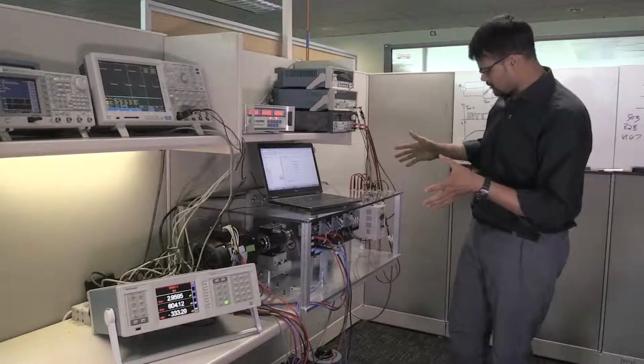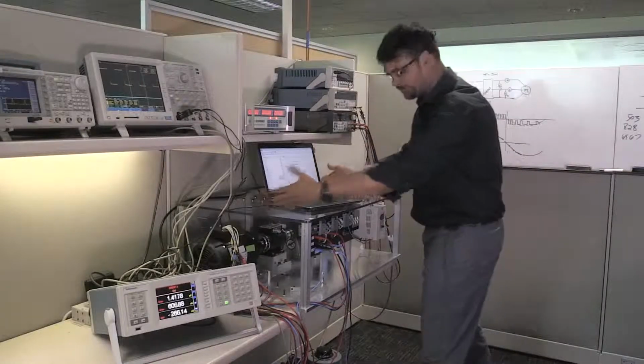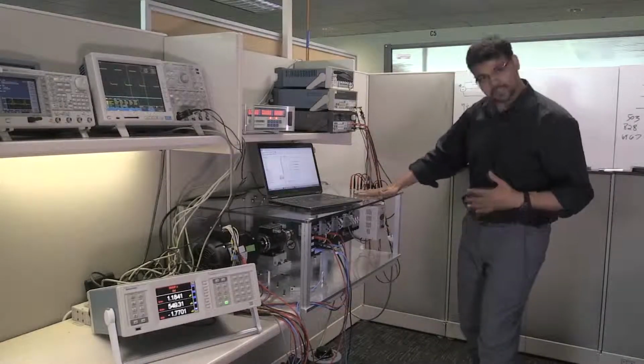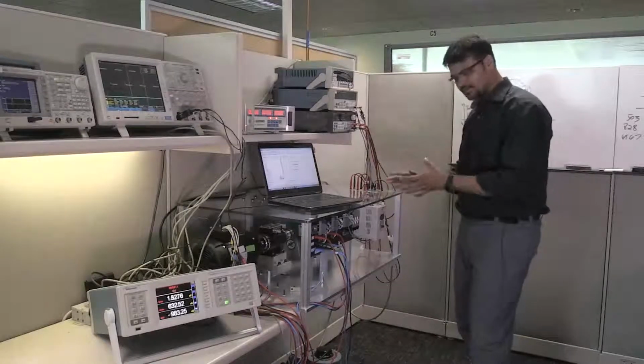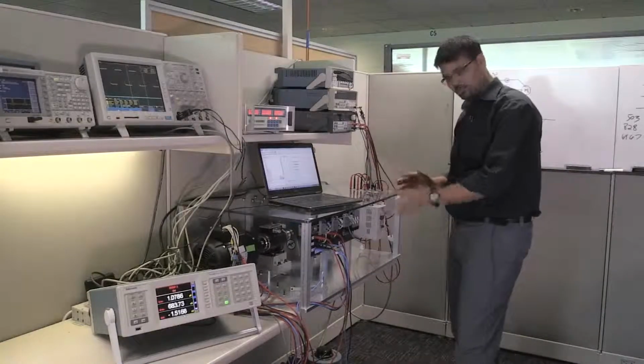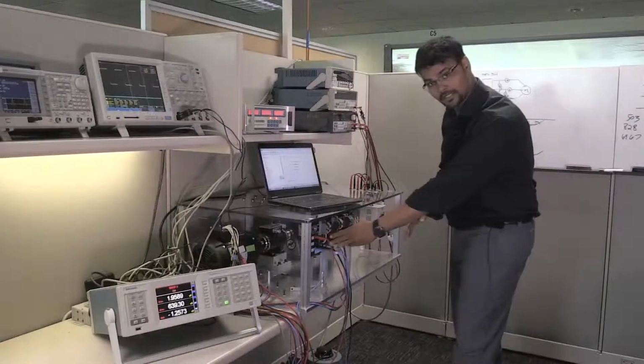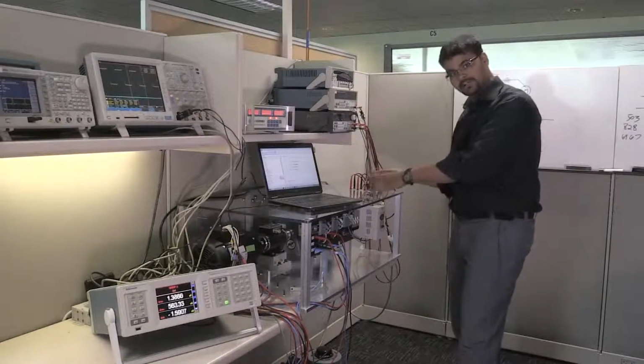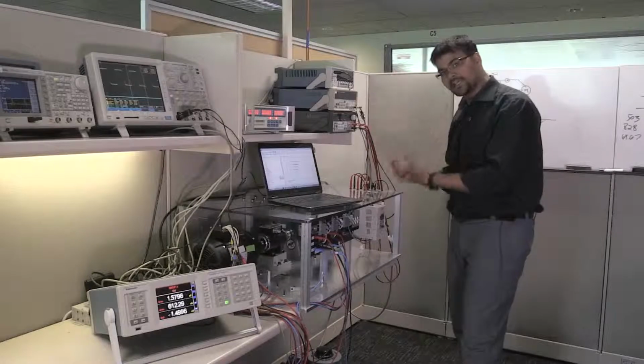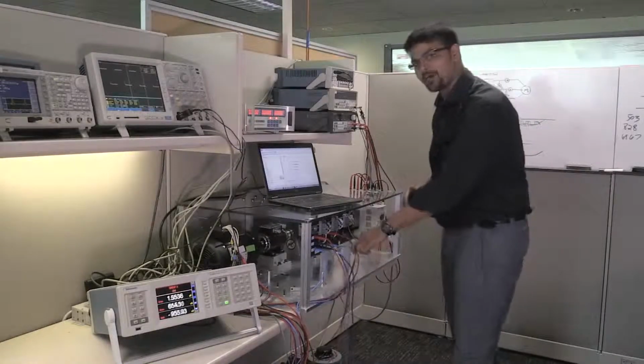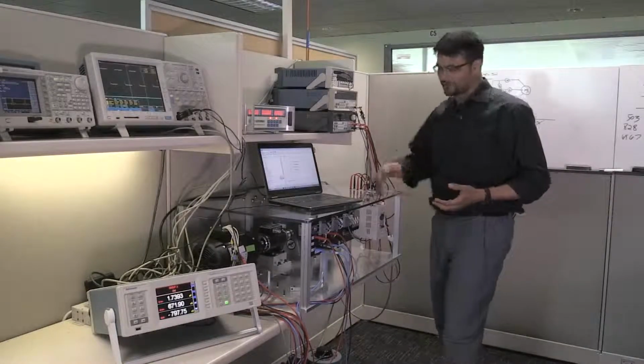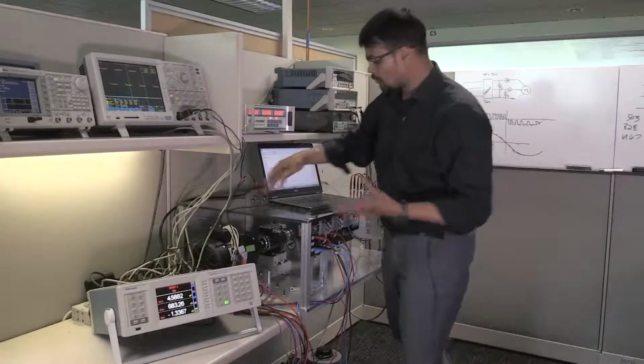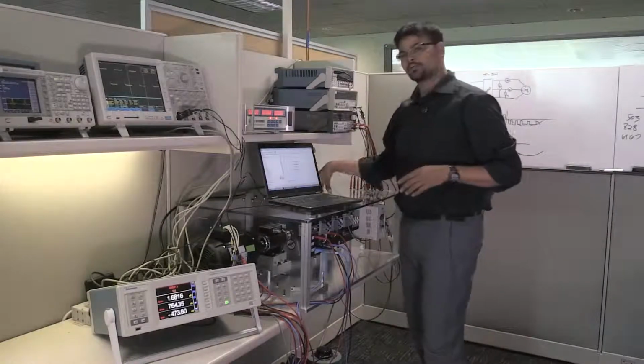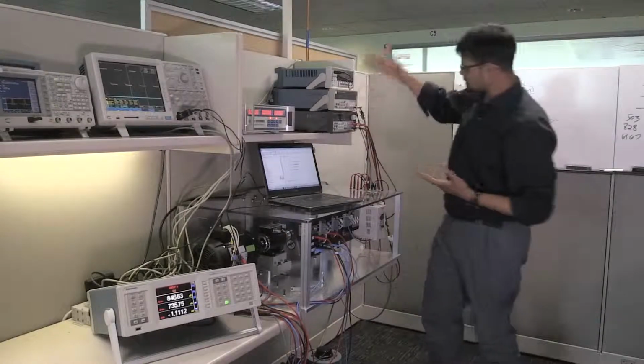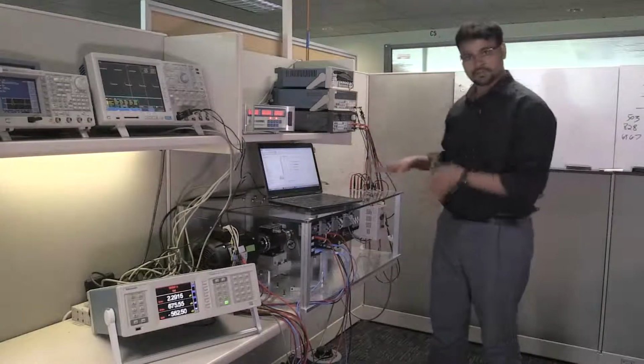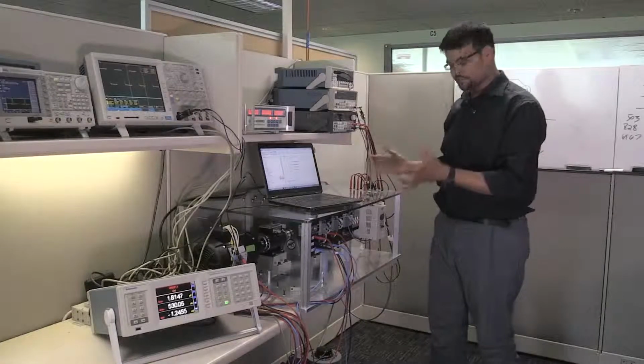What we have here is a three-phase motor driven by a GS2 AC drive. It takes three phases from the AC source, and the GS2 motor drive processes that AC input into a high frequency PWM output that goes into this motor. The motor is then driven through the shaft into the dyno system. As you can see, we have our power supplies for the dyno, for the GS2, and so on. That's our system.